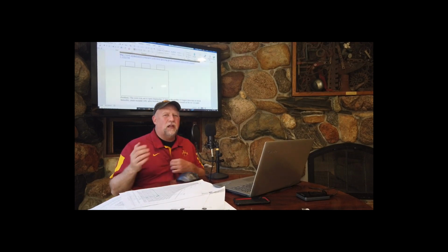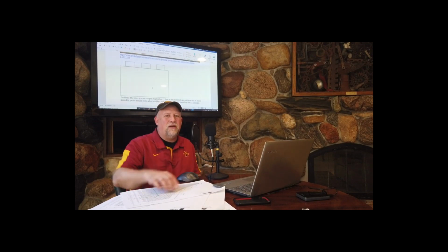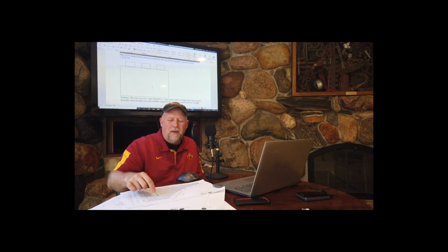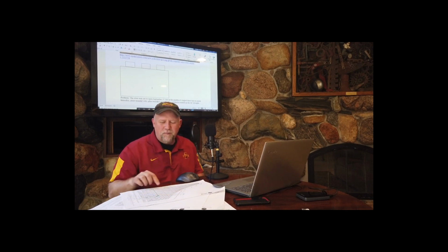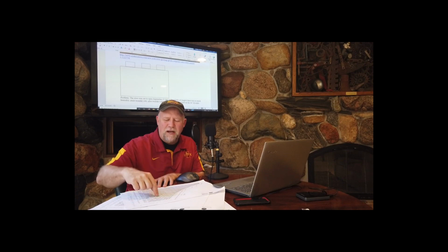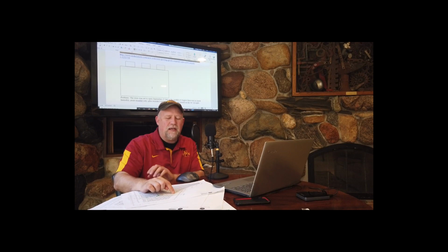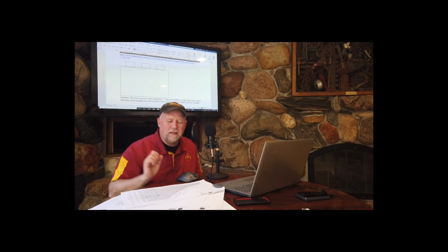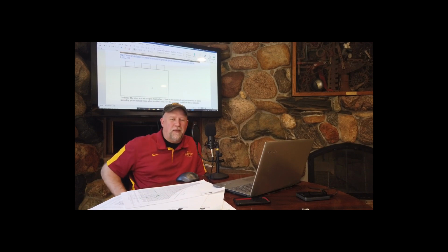They turned this on at night and let it run, and all of that load wasn't there. In other words, it cooled it down and then shut off. And so basically, if you just look at 75 degrees, it's straight over. Well, what happens if you go straight to the left from 95 degrees Fahrenheit, 50% relative humidity, and you stop at 75 degrees? What is your relative humidity? You'll find your relative humidity is about 90%, which is the problem that they ran into. In other words, nothing's drying out. It's cooler.